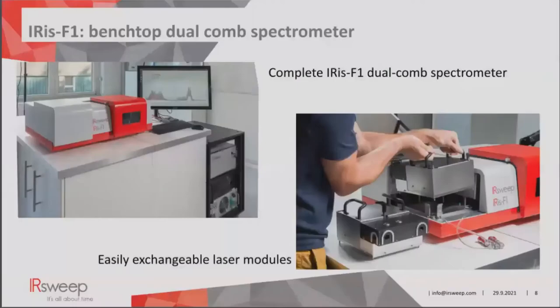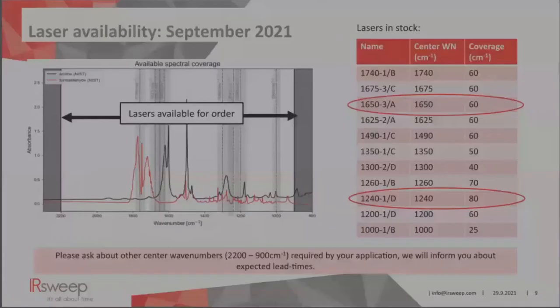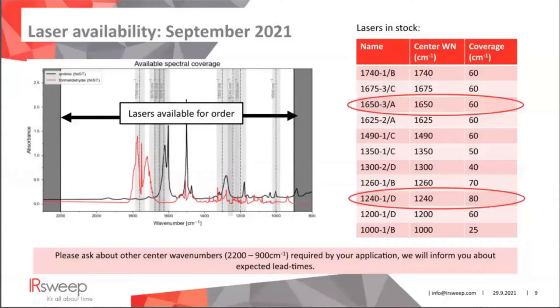One of the cornerstones of the Iris F1 is the ability to change a laser module, which can be done in 30 seconds, followed by stabilization of another 10 to 20 minutes depending on temperature changes. After that, you are ready to measure again with high time resolutions and great SNR in the microsecond time regime.